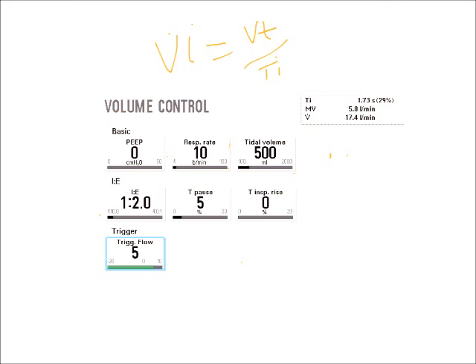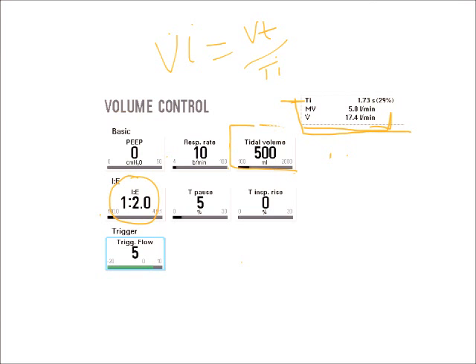We can see this little smart window. Newer ventilators will have smart windows which will do the math for you. So if I manipulate one setting, say my IE ratio, it's going to change my inspiratory time. Here's my inspiratory time measurement, and you can also see my calculated flow rate down here, which is 17.4 liters per minute. So if I needed to change this flow rate, I could change two things: I could change my tidal volume, however since I'm in volume control ventilation I probably do not want to do that. I could also change my respiratory rate, but to change my flow I'm going to have to manipulate my IE ratio.